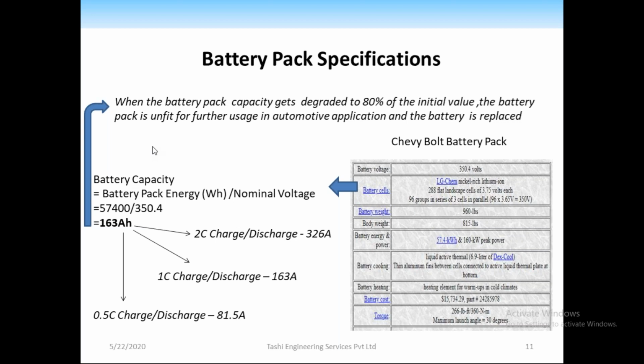Before making any calculations, we need to be thoroughly clear about the C rate. If we are charging or discharging the Chevy Bolt at 326 amps, we say we are charging or discharging at 2C rate. 1C rate corresponds to 163 amps, whatever your capacity is. If you are withdrawing or inputting 81.5 amperes, that means you are charging or discharging at 0.5C rate.